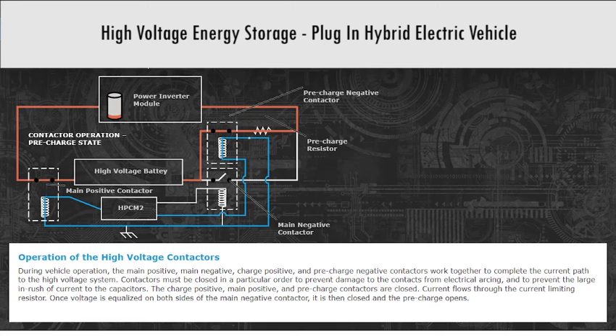During vehicle operation, the main positive, main negative, charge positive, and pre-charge negative contactors work together to complete the current path to the high voltage system. Contactors must be closed in a particular order to prevent damage to the contacts from electrical arcing and to prevent the large inrush of current to the capacitors. The charge positive, main positive, and pre-charge contactors are closed. Current flows through the current limiting resistor. Once voltage is equalized on both sides of the main negative contactor, it is then closed and the pre-charge opens.